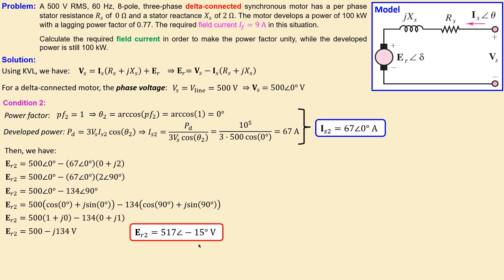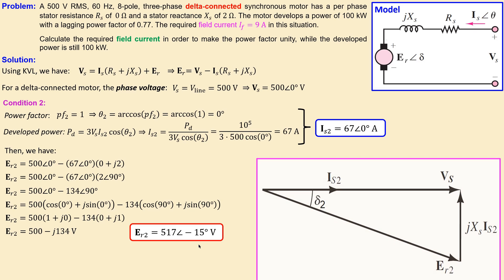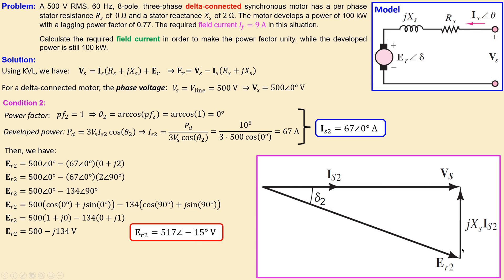Looking at the phasor diagram for condition two, the stator current is in phase with the phase voltage, which is required for unity power factor. The phase voltage is 500 volts, the stator current is 67 amps, and theta two is zero degrees. The back EMF is now 517 volts — larger than the phase voltage. The torque angle is minus 15 degrees, and the voltage across the reactance is 134 volts.